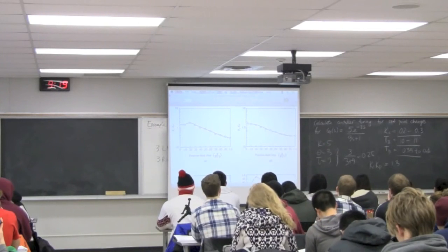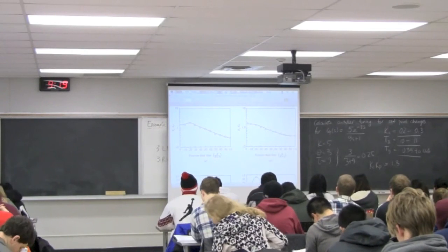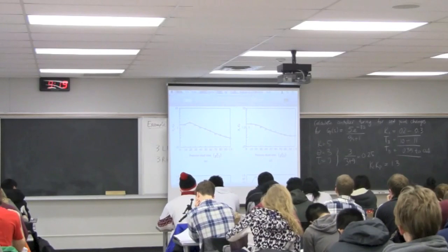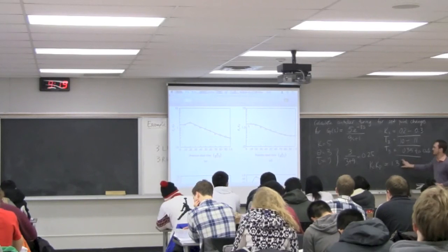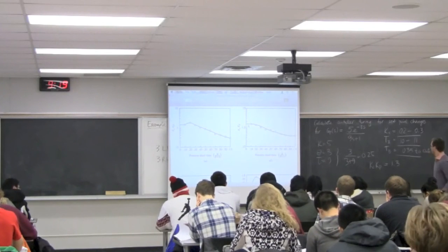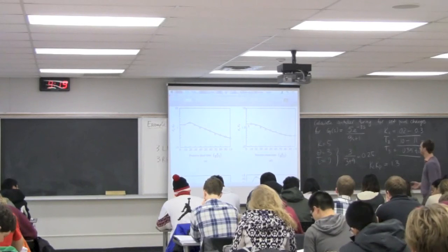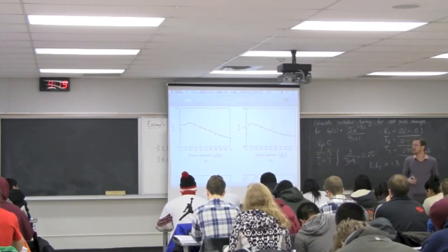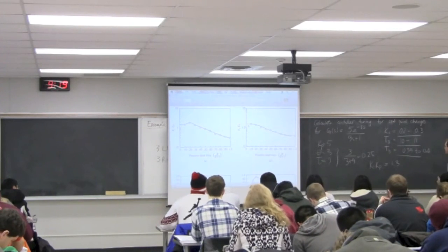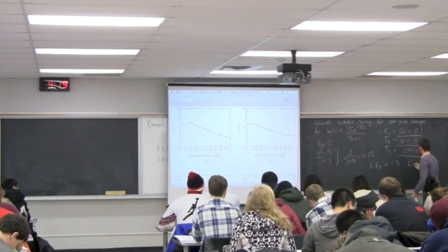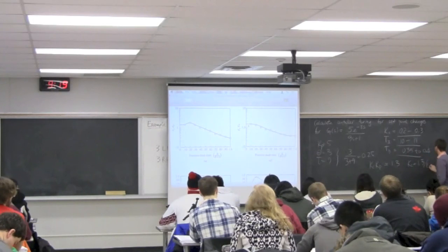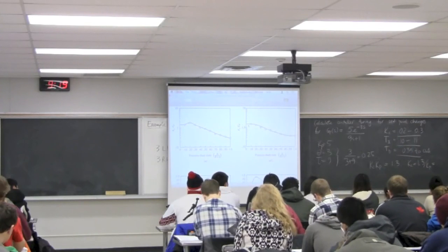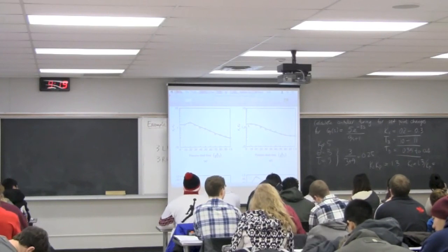That little notch above it is 2. This is the log axis, so it's 1, then a fairly big jump to 2, 3, 4, up to 10. So we're around 1.3 for KC times KP. KP refers to my process gain, so I can calculate that KC is equal to 1.3 divided by KP, which in this case is a number in the order of 0.2 to 0.3, depending on how you read it. Everyone clear on this?